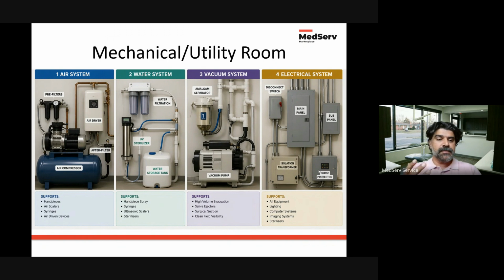The compressor typically is a medical grade air compressor, meaning that it is run oilless. It's not just some shop air or some compressor they bought from Harbor Freight. There are implementations for filters to eliminate moisture and oil contamination, so that it doesn't further damage pieces of equipment or handpieces downstream.